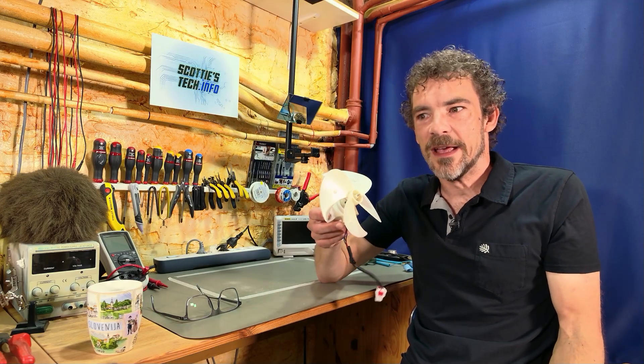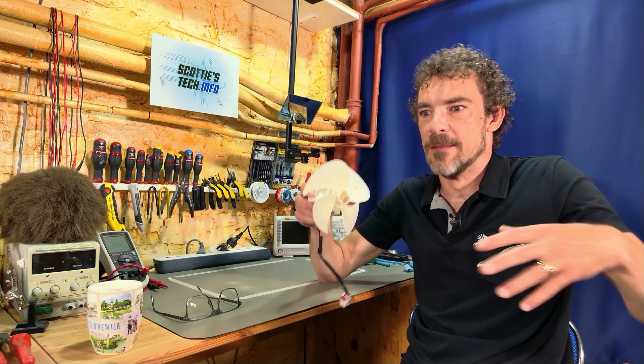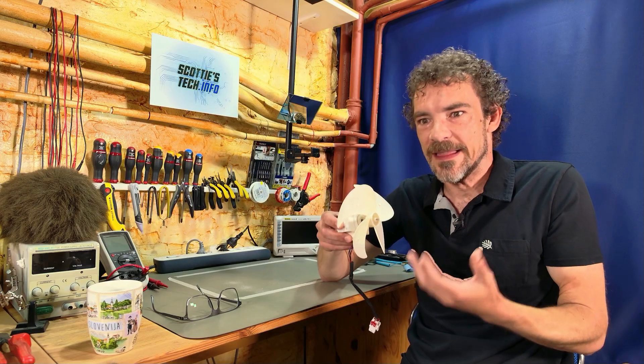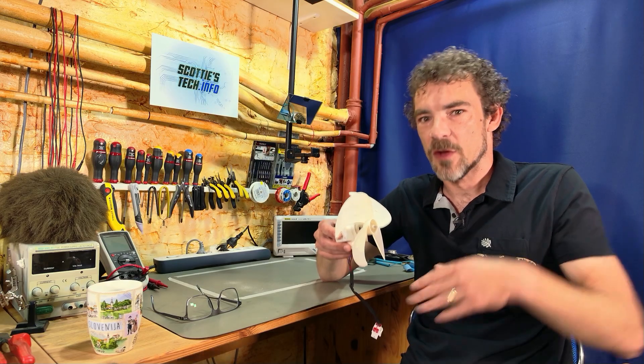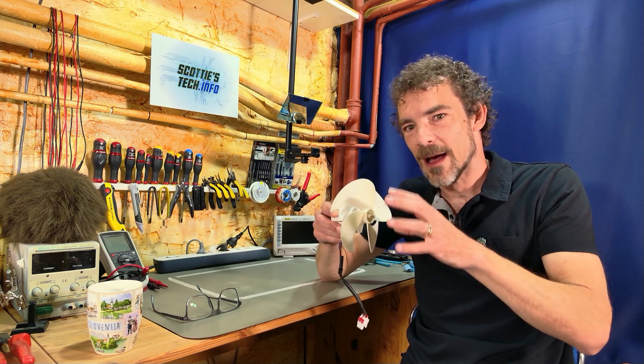This rotational inertia is an integral part of how AC generators work — it's just a function of the fact that they're big, massive, really heavy, rotating things. Historically, this is what has provided a lot of the stability to the grid, because all that rotational inertia acts as a two-to-seven-second buffer that allows the power plant time to compensate and get to the new higher level of power required.